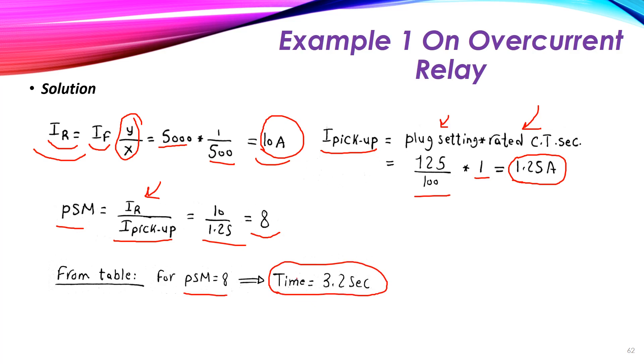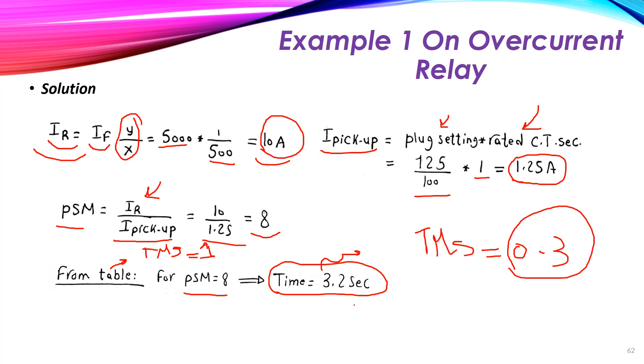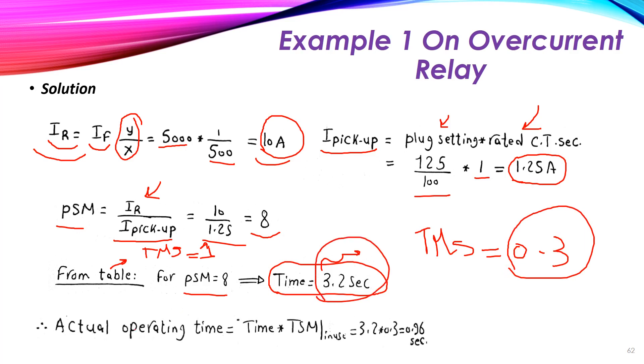However, this 3.2 seconds is the time at TMS equal to 1, and the required TMS is 0.3. So we multiply: actual operating time = 3.2 seconds × 0.3 = 0.96 seconds. This is the actual time taken by the relay to clear the 5000 ampere fault.